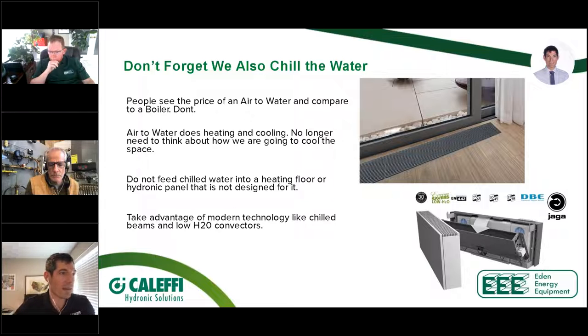But it's a great way to go when people are looking to do the coolest version of hydronic in a space where they've got a lot of glazing, like we talked about with the slide at the beginning. This is not a cave if you've got ceiling-to-floor glass there. But we still need to heat this space. How do we do it? We can't put a panel radiator in front of a sliding glass door. This little trough is a really cool way to do that. And there are some cases where you could, within reason, run some chilled water through that as well, since we're additionally moving air across it. But yeah, don't just replace your baseboard in your house and run chilled water through it.